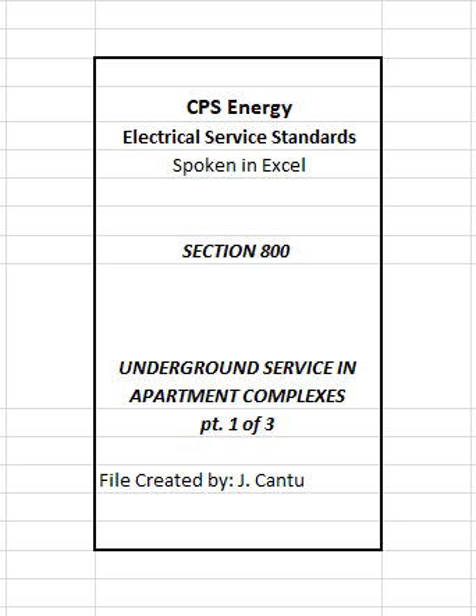803 1 Transformer pads. Pads for single-phase transformers up to 167 kVA shall be precast concrete and shall be furnished by CPS Energy. For 250 kVA transformers, customer shall have the option of either having CPS Energy provide the precast concrete pad or they may elect to build a 6-foot x 6-foot concrete pad per CPS Energy specifications. For transformers larger than 250 kVA, the customer shall build a 6-foot x 6-foot concrete pad per CPS Energy specifications. All transformer pads must be installed such that the surface of the pad is 6 inches above finished grade. In addition, customer shall furnish and install one 5/8-inch x 8-foot ground rod in the transformer pad. CPS Energy will install all necessary ground rod connectors.